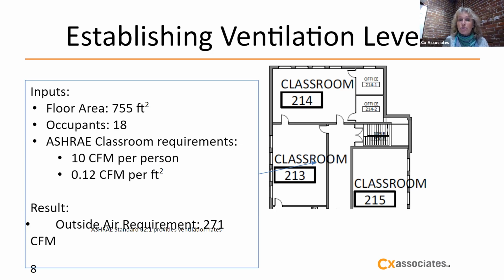In this case, we've taken a classroom as an example, where for the occupants you have a requirement of 10 cubic feet per minute of fresh air per person. So you would multiply that 10 CFM times the 18 occupants to get what you need for the people. And then there's also the 0.12 CFM, cubic feet per minute per square foot, for the area. And for this example, we conclude that the outside air requirement is 271 cubic feet per minute. And so we recommend that you get someone, whether it's a contractor, a commissioning agent, or a mechanical engineer, to calculate what your spaces need for ventilation for the number of occupants you have.